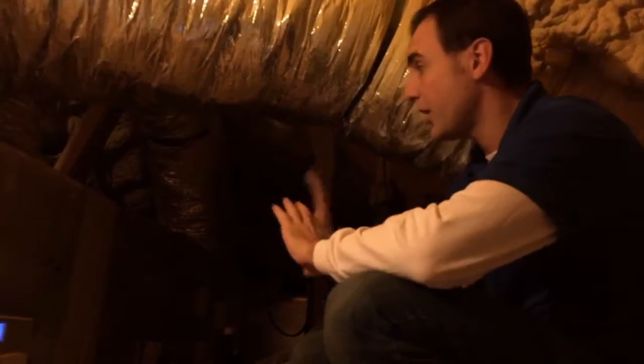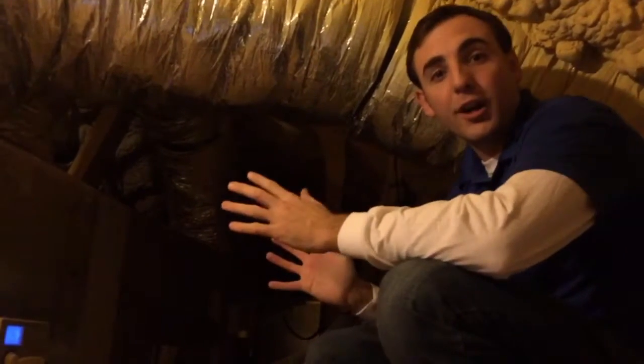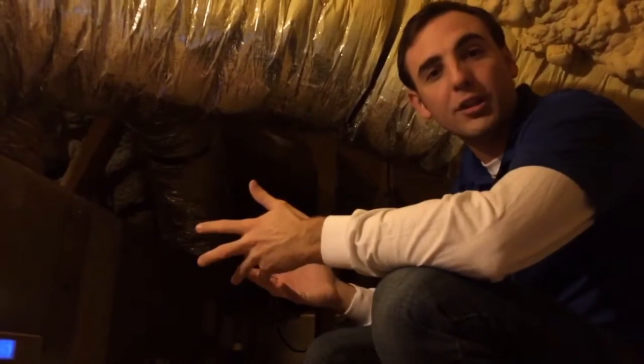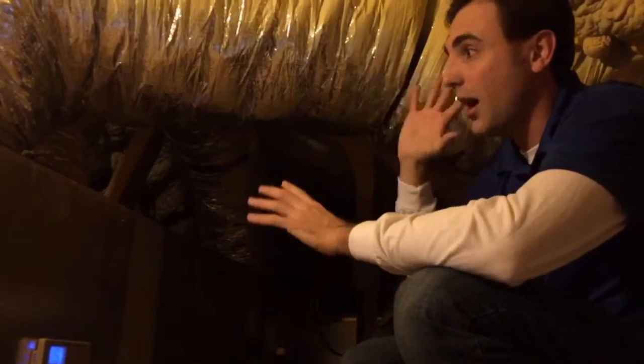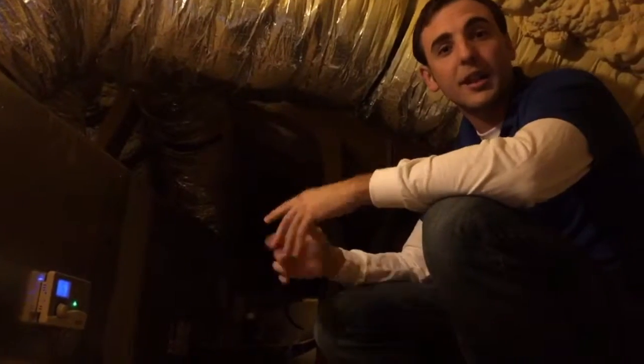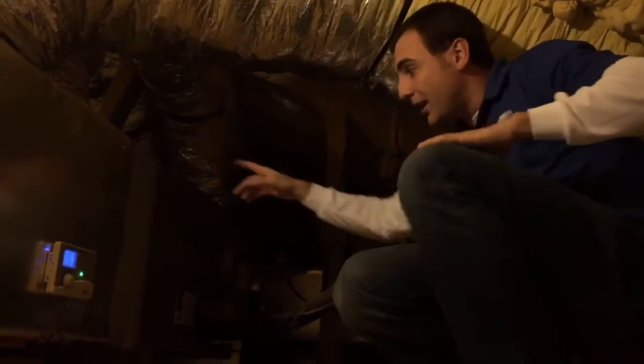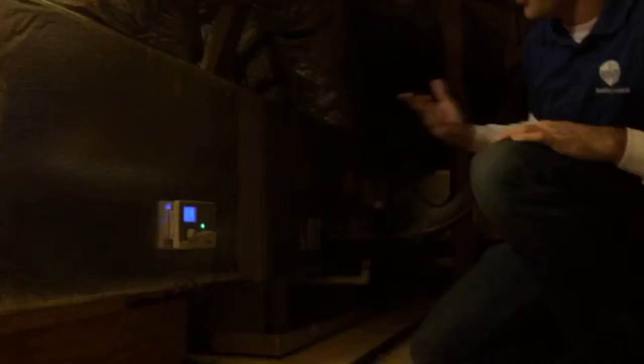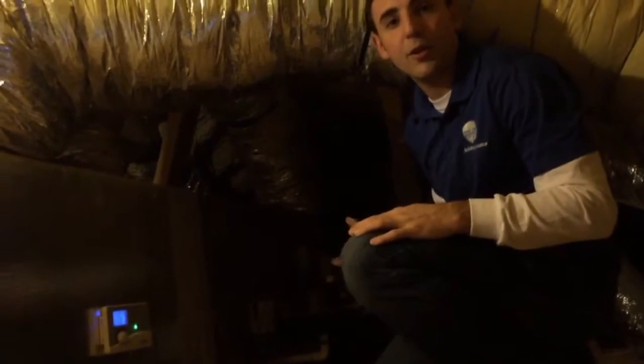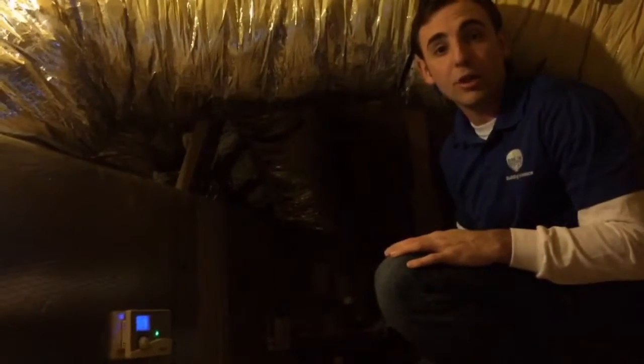So one of the first things I look at when I'm measuring airflow is the ductwork and the unit in the attic. I want to make sure that everything looks like there's going to be a good amount of airflow going through the system. There's no restrictions. I look at how many return ducts are going off the system for a later test that I'm going to do, like duct leakage and things like that. I also look at these seams here on the return and the supply side, as well as unit penetrations like this. You want to make sure that all those things are sealed, because all of that affects airflow, static pressure, and unit efficiency in general.